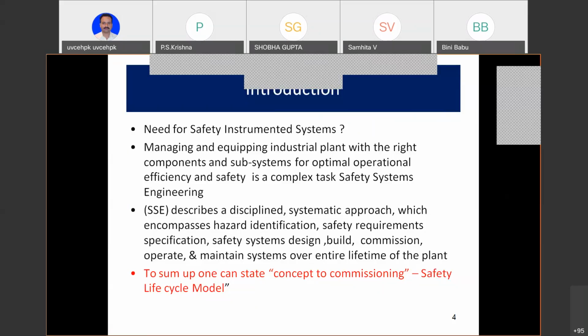So safety systems: when you have been told today that you have to have a safety instrument system for that small hypothetical plant, how would you go about it? You will go about it in a very systematic way. That is called, in philosophy, concept to commissioning. That is, you conceptualize, you design, you build, commission, operate, maintain, and last but not least, when the time has come for total upgradation or discarding the plant, you have to write a procedure for decommissioning also. To sum up, one can say concept to commissioning of the life cycle model.